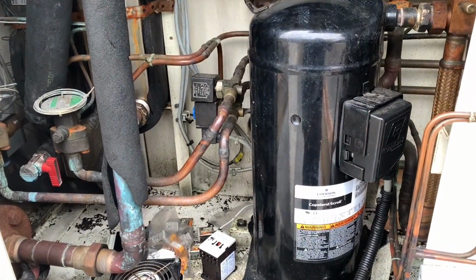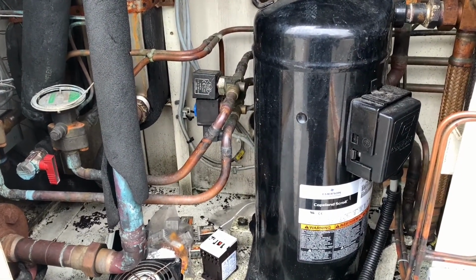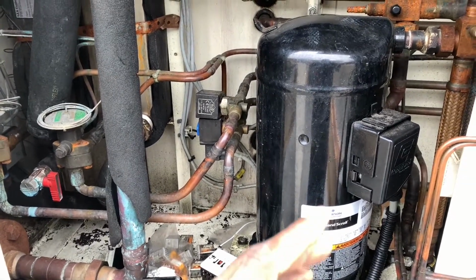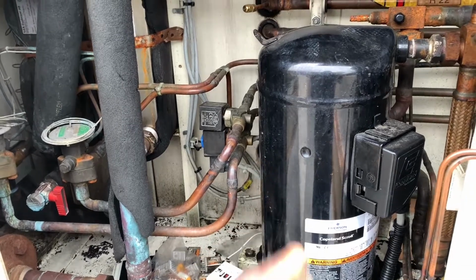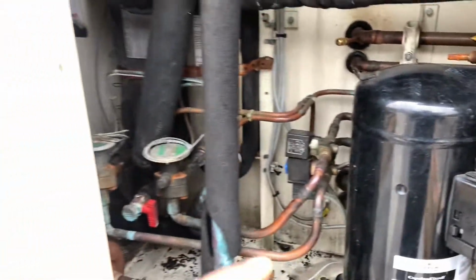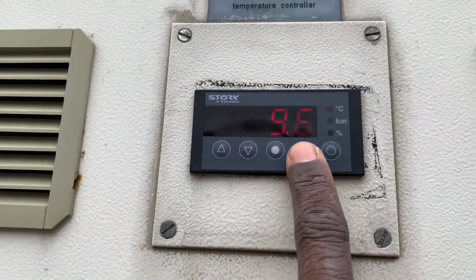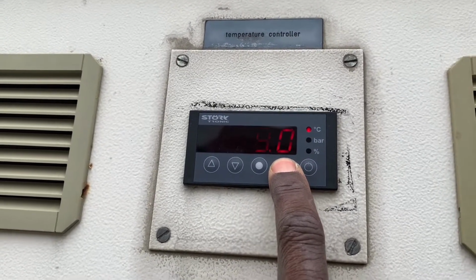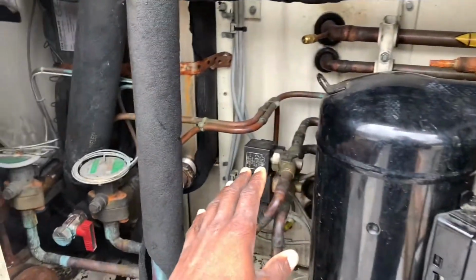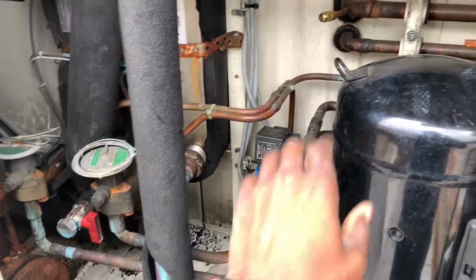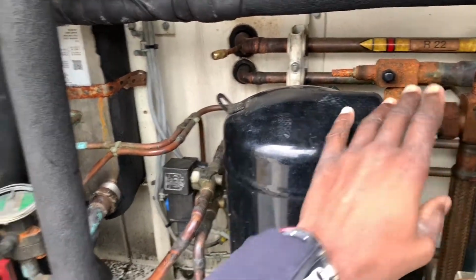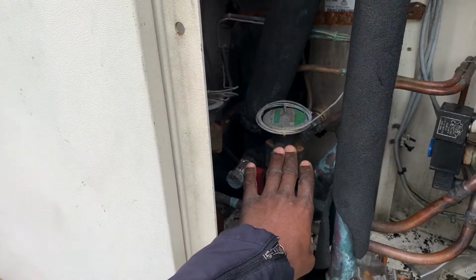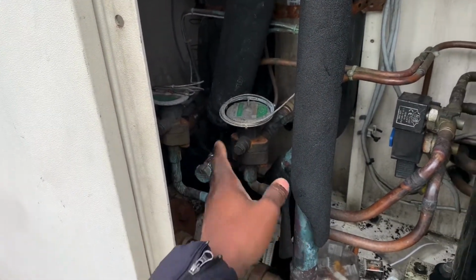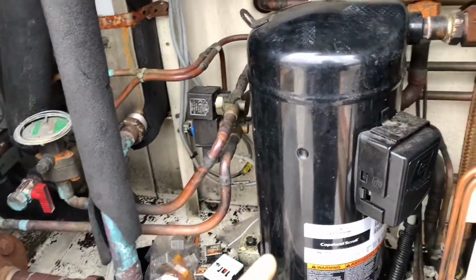And note, the compressor doesn't cycle off even though it reaches set point, because it uses a hot gas bypass for capacity control. So whenever the temperature reaches close to set point, which is currently 9°C, the hot gas solenoid will open and it will send the discharge gas from the compressor straight into the evaporator inlet or the TXV outlet, which bypasses the metering device and thus controls capacity.